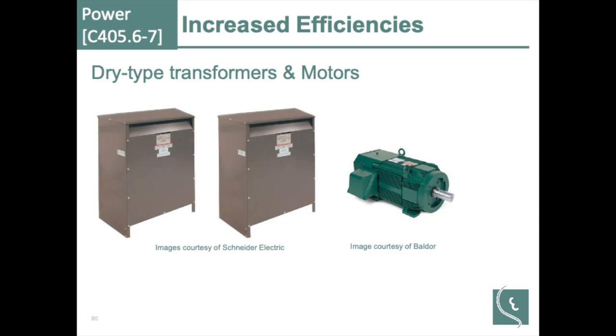And for motors, they now require NEMA premium motors. That used to be the high efficiency stuff. Now it's the minimum efficiency. And now we're just beginning to see come to market these new hybrid motors, which are a combination of induction and permanent magnet motors. And as you can see, they look very different from a regular motor. So it's kind of easy to tell when one of these is involved. But transformers, that's a tough one.